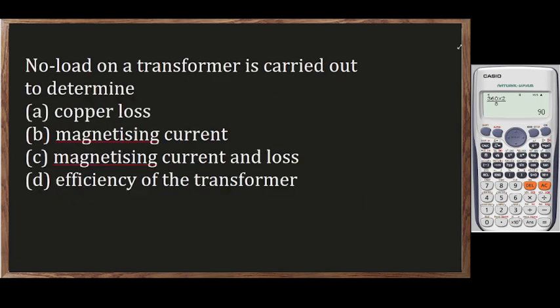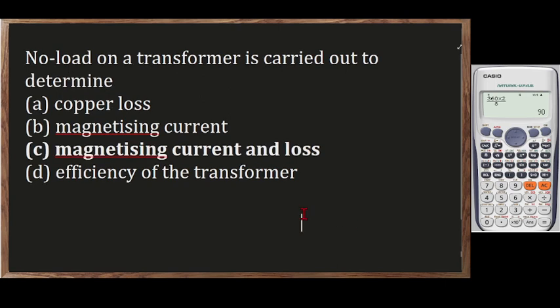Next, the no load test on a transformer is carried out to determine the blank. So, that is the open circuit test, no? Or the no load test. The copper loss, the magnetizing current and loss, or the efficiency of the transformer. No? The correct answer for this one is letter C, the magnetizing current and loss. So that is the hysteresis and the eddy current loss. No? So that is the other term. No? The magnetizing current, this is the eddy current loss, and yung isa naman is the hysteresis loss.